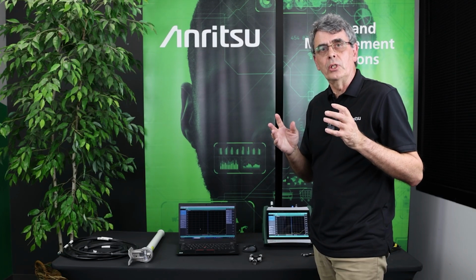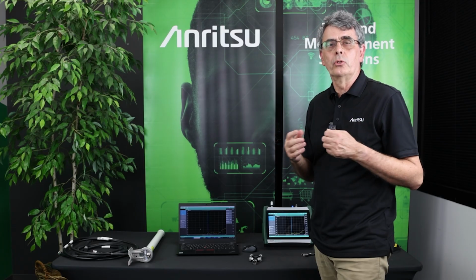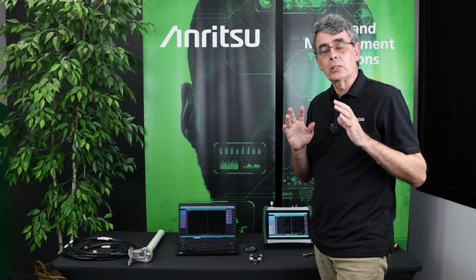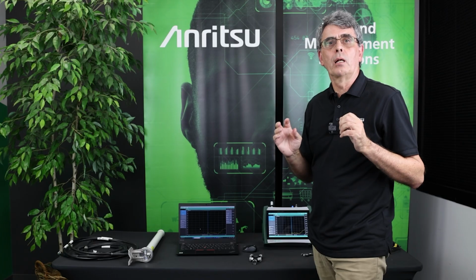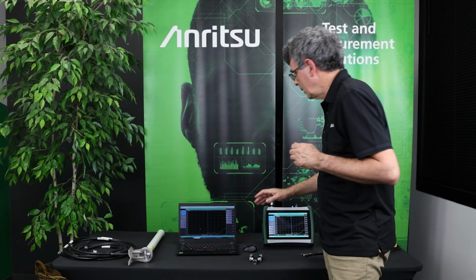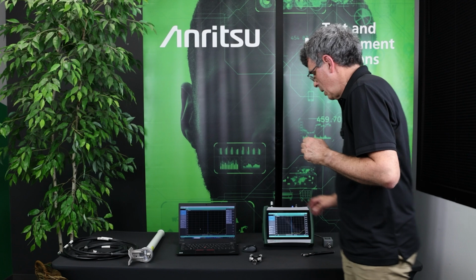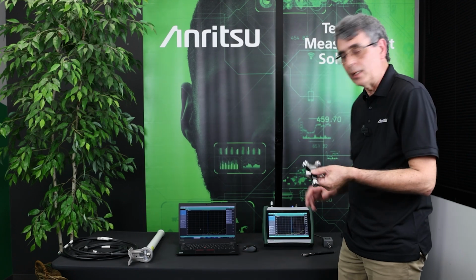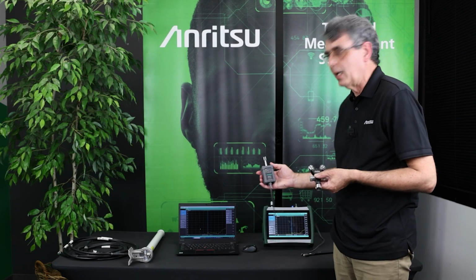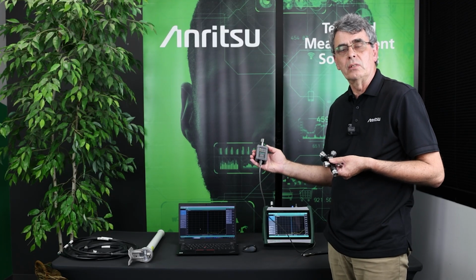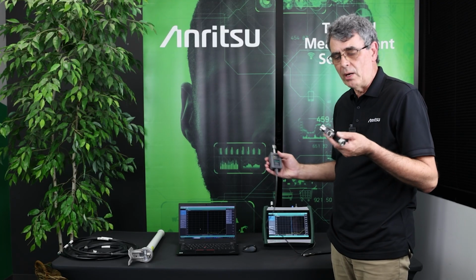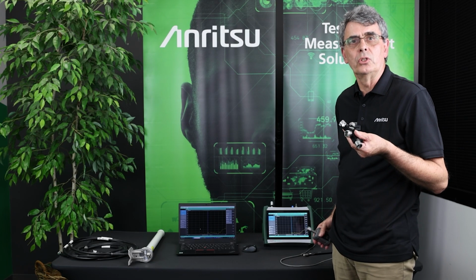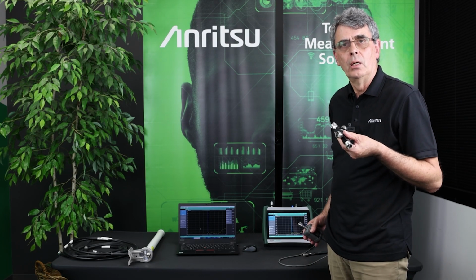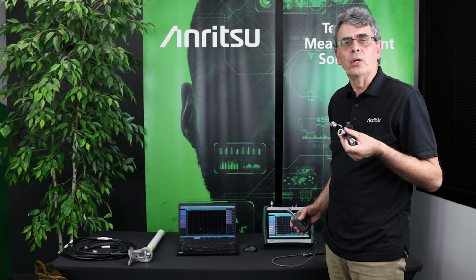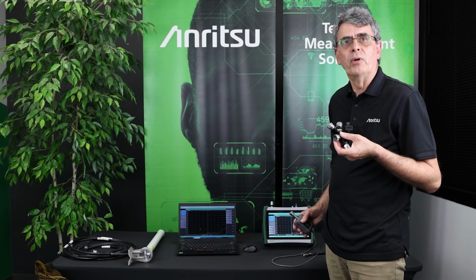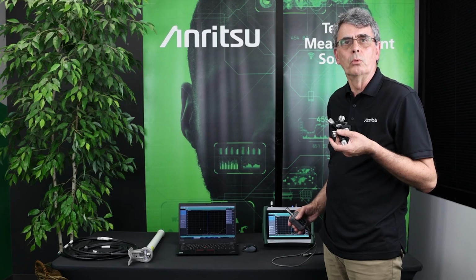So to summarize, we have three calibration options. We can use the factory cal, the ReadyCal, straight out of the box as soon as we turn the instrument on. And that's fine as long as we're working at close to room temperature and we're making our measurements at the test port. Otherwise, we need to use either the mechanical cal device or the InstaCal device. The InstaCal device is faster and more convenient. The very best performance up to 6 gigahertz is achieved with the mechanical calibration, but in reality, all three of those calibration processes give you very good results in most normal operating conditions.